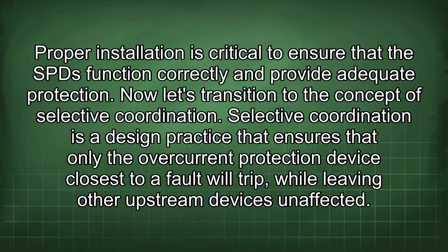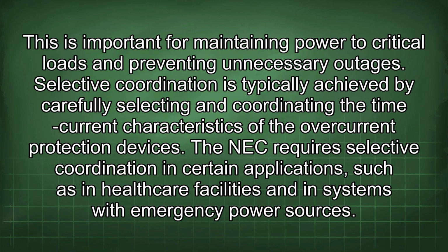Now let's transition to the concept of selective coordination. Selective coordination is a design practice that ensures that only the overcurrent protection device closest to a fault will trip, while leaving other upstream devices unaffected. This is important for maintaining power to critical loads and preventing unnecessary outages.